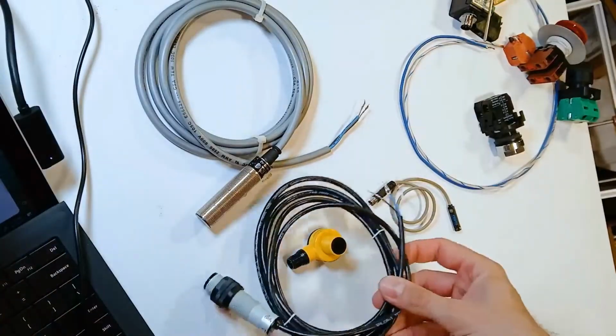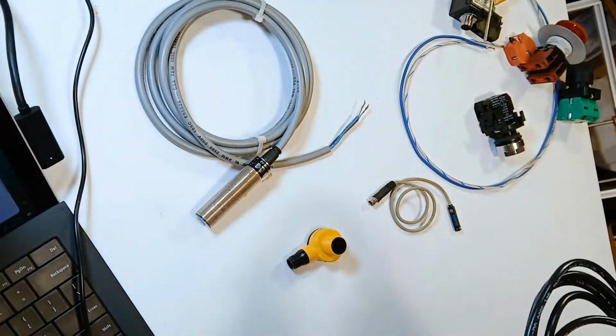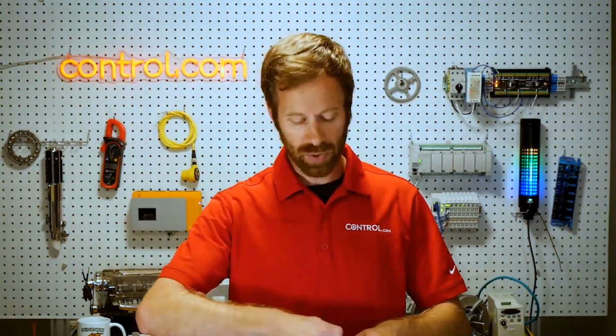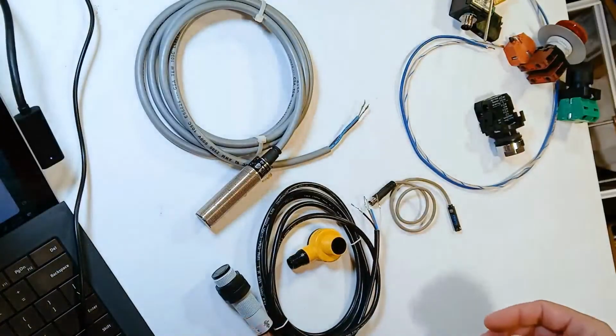So in those cases, a little bit of a difference here is that we don't have any adjustments to those sensors. We don't have a control knob or a potentiometer to be able to adjust the sensitivity of an analog device. You buy it and the data sheet says 0 to 10 volts is a window between this range and this range. All of those adjustments, the thresholds, things like that, those are all done in the software. Since we can return back any value we want, we simply allow the software to compare the current value to a threshold value that we want, and then energize output devices based on that.